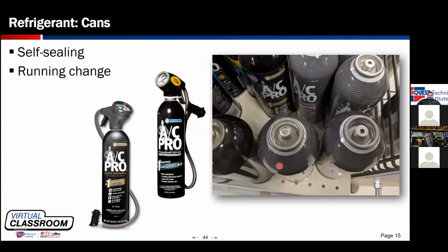But you can see the can on the left here. This is an old style small can. It's a punch top style can. So the tap for this can, when we go to use it, would have a pin that we would drive through this seal to release refrigerant. The problem with that is an air conditioning system's charge generally is not even multiples of a can. So you wind up with a partial can that has refrigerant in it. So if I take that can off the gauge, now all of that refrigerant is going to vent into the atmosphere. Kind of defeats the purpose of a lot of what we're trying to do.